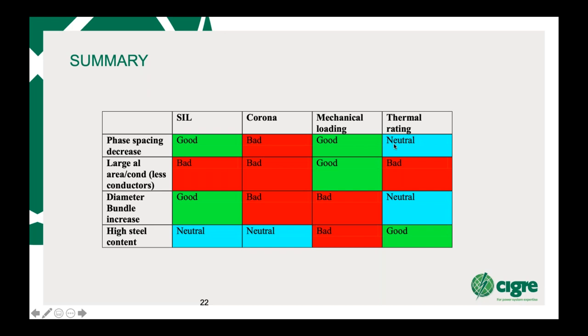For large area aluminium conductors, in other words, instead of having a 6 bundle, you've got a 4 bundle with bigger conductors, the surge impedance loading is bad because it likes to have more subconductors in the bundle. The corona is bad because it likes to have more subconductors in the bundle. Mechanical loading is good because it has lower wind load. And for thermal rating, it's bad because you actually get far better cooling per conductor if you have more in the bundle. So a quad bundle with the same aluminium area as a twin bundle will actually give you a higher thermal rating, even though it's the same aluminium area.